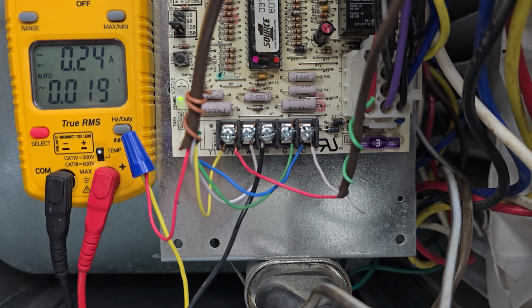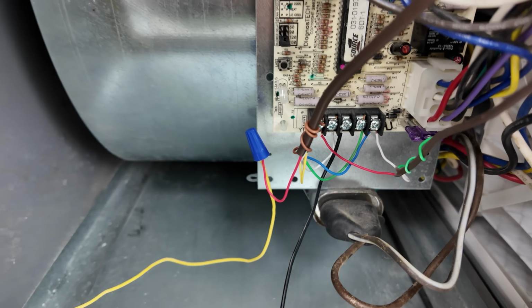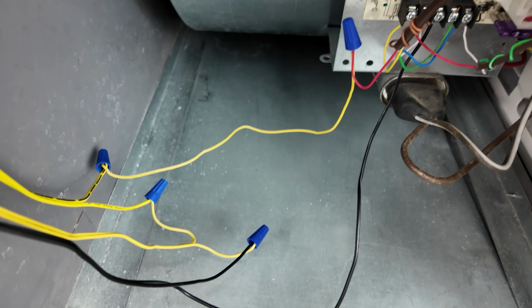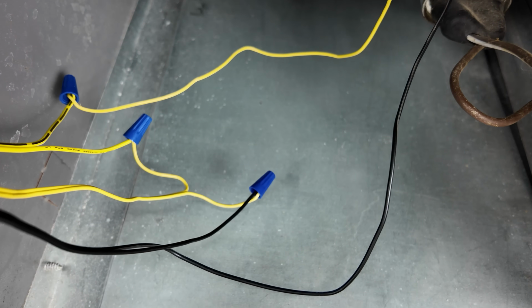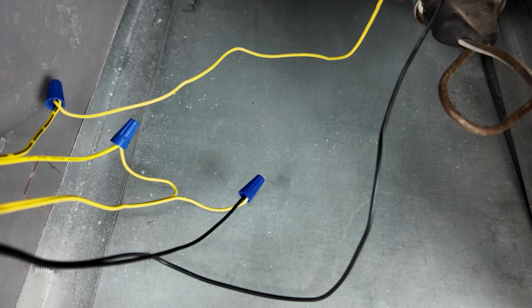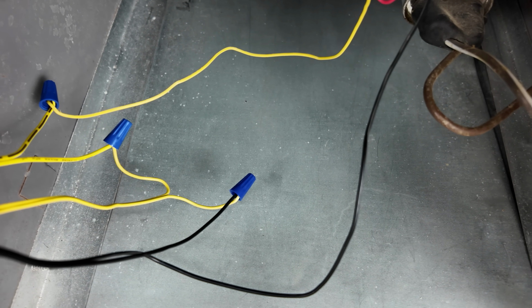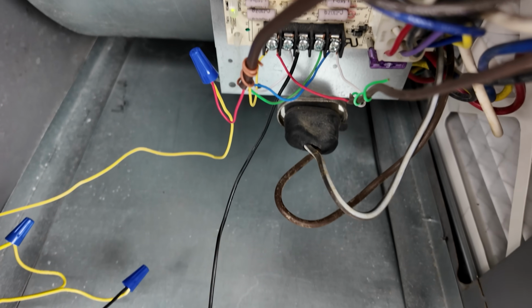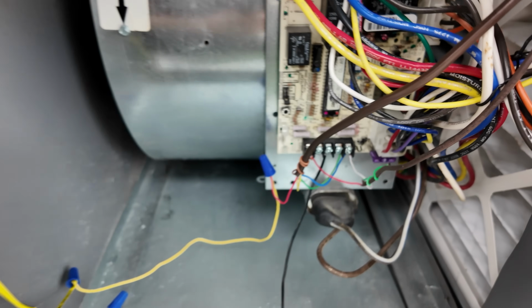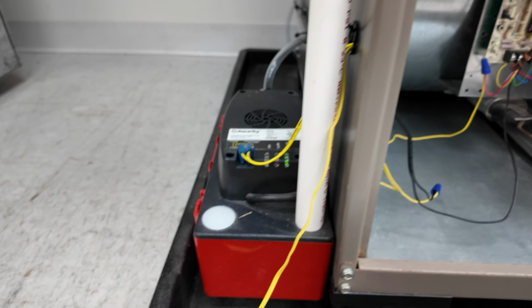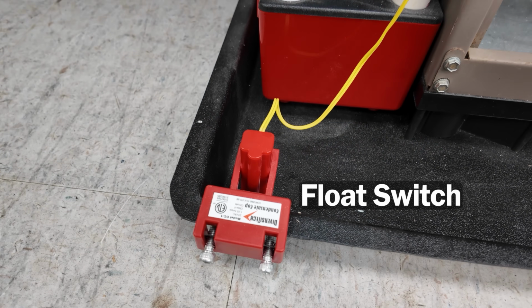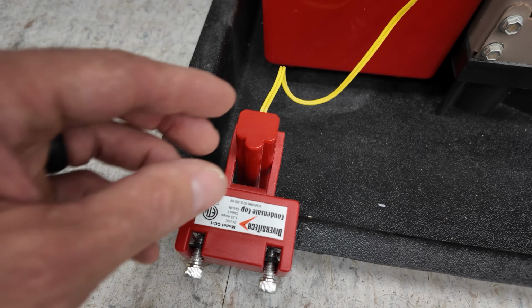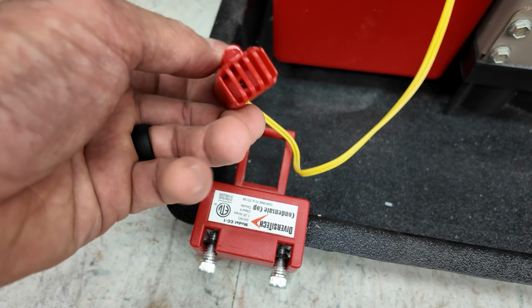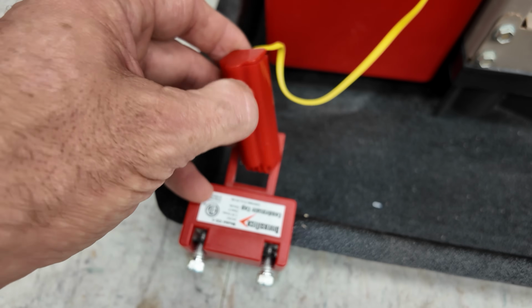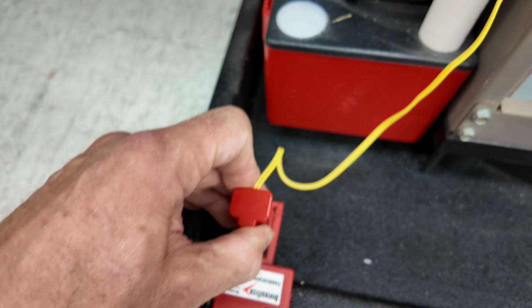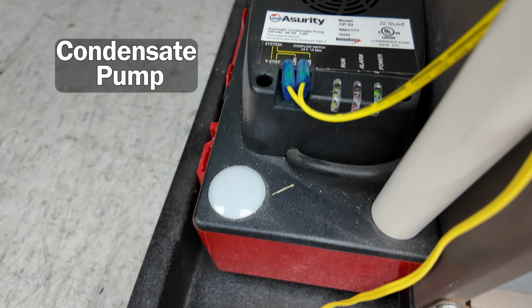So let me show you what those switches look like. So starting right here in this blower compartment, you see that we have 3 wire nuts. So there's 3 separate switches that are wired in series. It's going through all 3 of those and then back over to that terminal on the R of the circuit board. So what we have here is a float switch for the condensate pan, and so that's located right here. And so if we were to take this out, you can see that there's a float inside, and so that could be the issue.